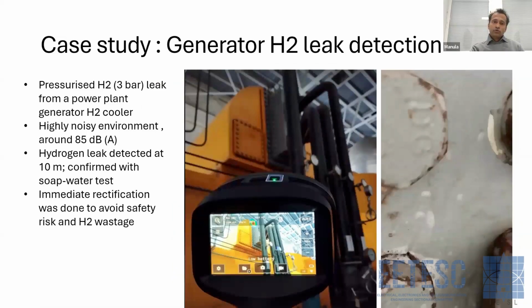Now let's have a look at some case studies for leak detection. In this case study, we have generator hydrogen leak detection. These are large generators used, for example, in coal power plants, and they are cooled using hydrogen. Inside the generator there is pressurized hydrogen, usually up to 3 bar or 0.3 megapascal. Leaks to the outside environment pose a safety risk, and they also waste hydrogen, and generating hydrogen incurs cost. So it is very important to detect these leaks from both a safety and a cost point of view.